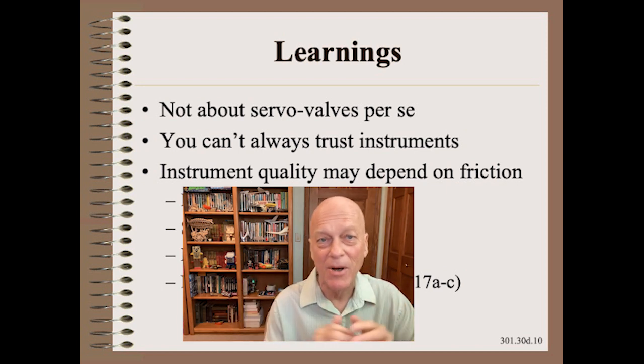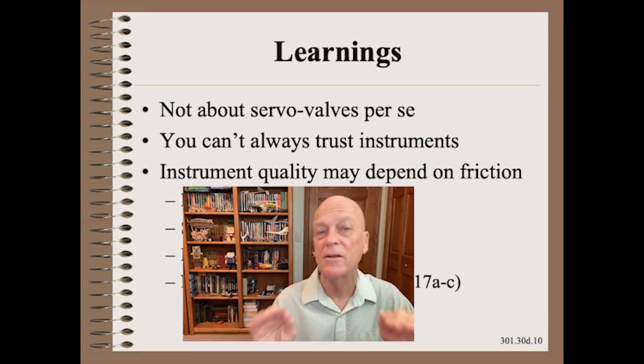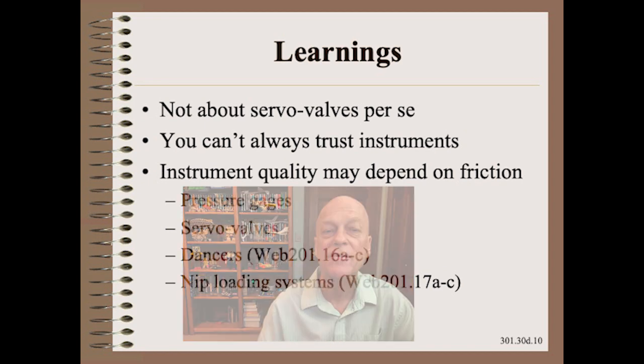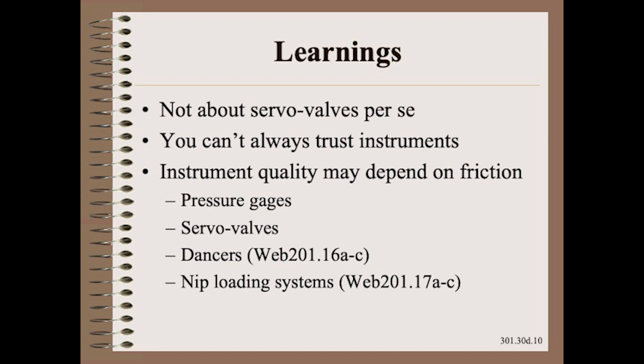As you should have guessed, this story is not just about servo valves per se. It is rather that, in general, you should not trust instruments until they are calibrated and rechecked on occasion. This story applies to pressure gauges, servo valves, dancers, and nip loading systems, and much, much more.